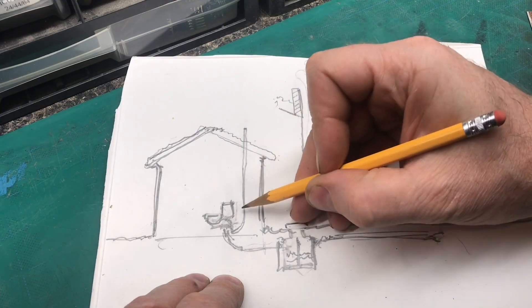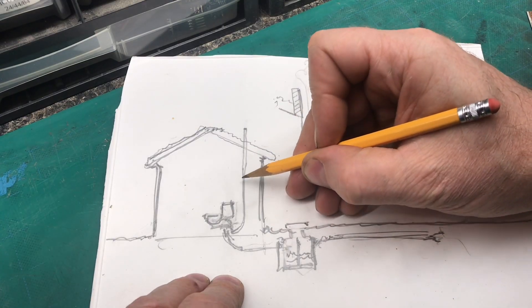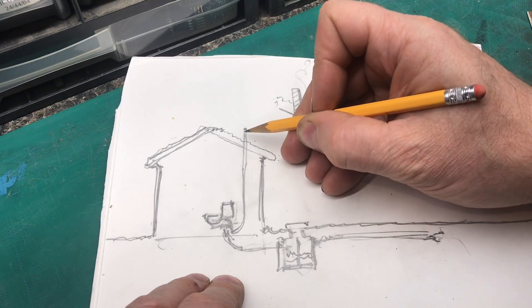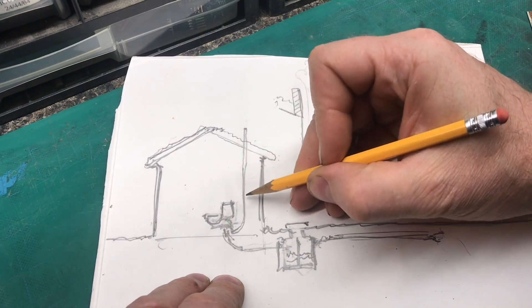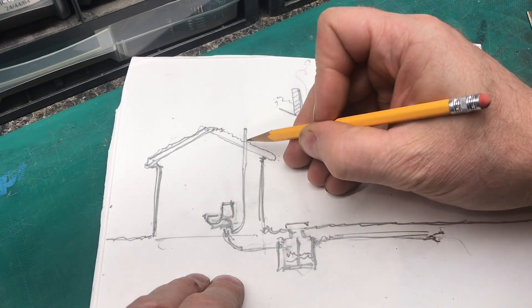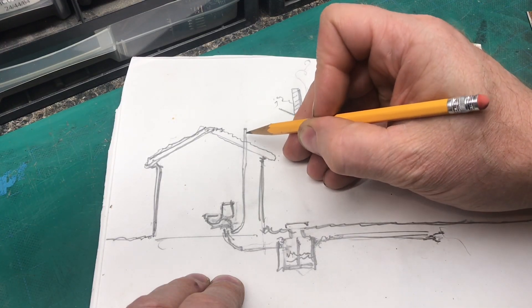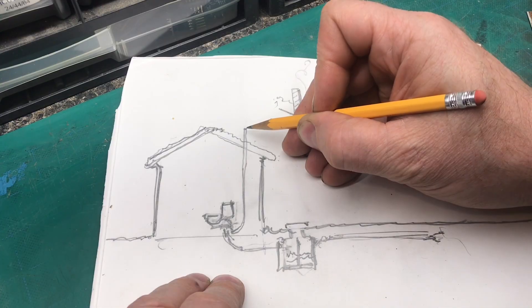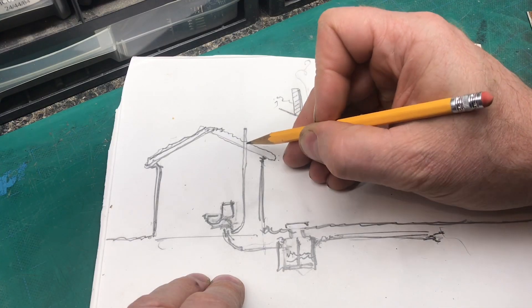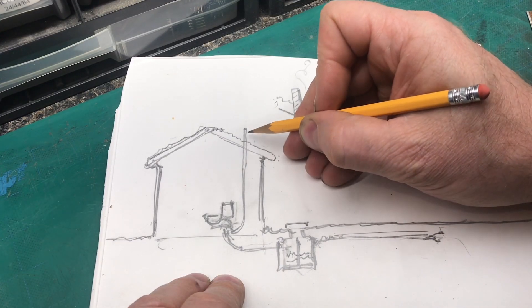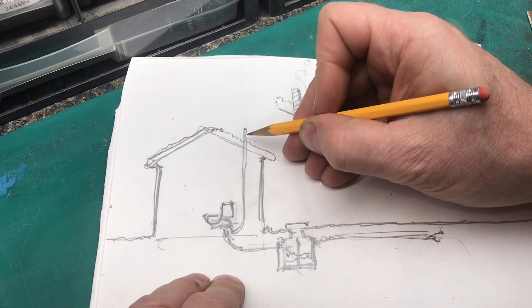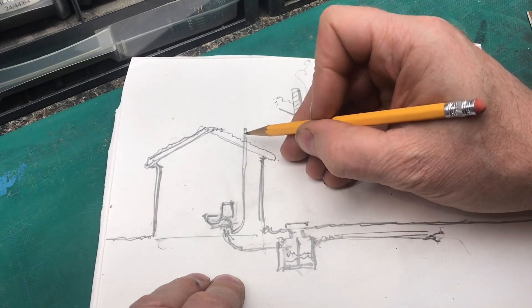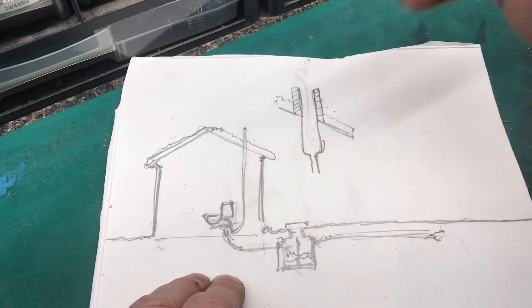...that warm moist air comes in from the warm side of your house, out the cold, and it starts to condense in here. And when it does condense, it starts to freeze and you can have a complete blockage in the pipe itself up here.